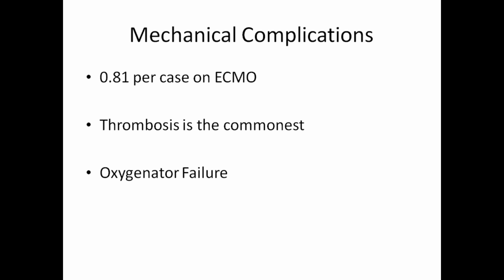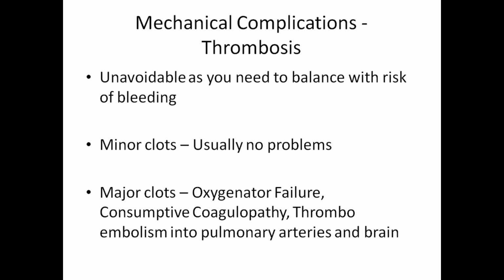So thrombosis is the commonest. Usually it happens in the oxygenator, or at the connectors in the circuit. So it's unavoidable, but minor clots are usually not a major issue. But major clots can impair the oxygenator. So one of the things we monitor on the circuit is the pre and post oxygenator pressure gradient. If the pressure gradient is increasing, that means the oxygenator is getting clotted, and you need to be ready with another oxygenator. Don't wait for it to fail completely. Another way is to check post-membrane gases. Generally, it should be more than 300. That means the oxygenator is working. If the oxygen levels are coming down to less than 200, that means the oxygenator is failing, and you need to be ready with another oxygenator.